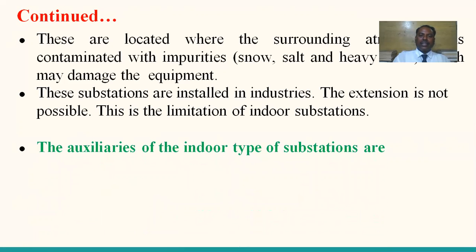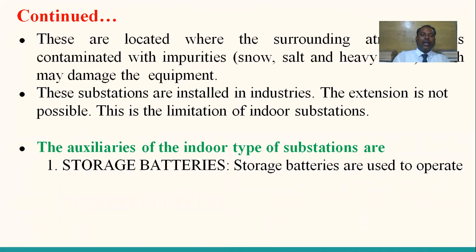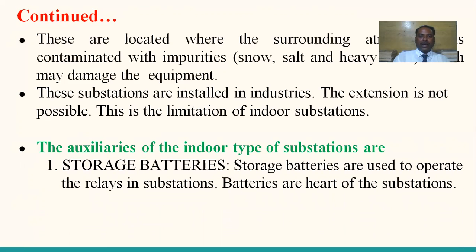What does the indoor substation have internally? Along with the equipment required for converting high voltage into low voltage, it also has some auxiliary instruments in the substation. Those are storage batteries. Storage batteries are important when the power has some trouble. Storage batteries are used to operate the relays in substations, and batteries are the heart of the substations, especially when we are talking about indoor substations.